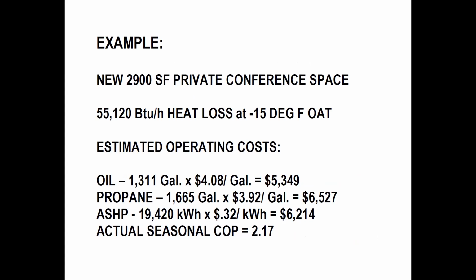Now, a couple of years ago, I helped one of the local contractors for a private conference space. And we figured out that the heat loss, based on our values of the windows and the walls and the roof, was going to be 55,120 BTUs per hour at minus 15. Estimated loss. I then ran the program based on those bin data because it was an air source heat pump system. And at that point in time, with the new, I actually changed this, didn't I? Well, actually, I have the 32 in there, the crappy kilowatt hour. So this would be much better, 0.32.